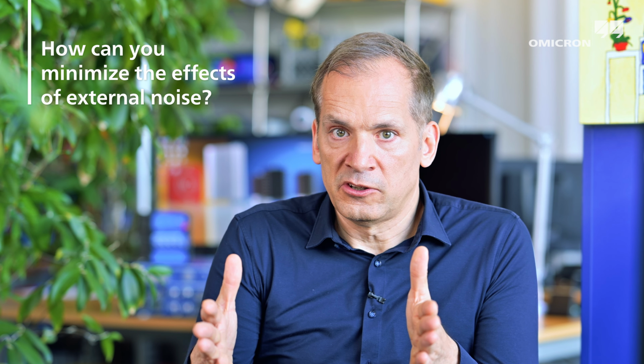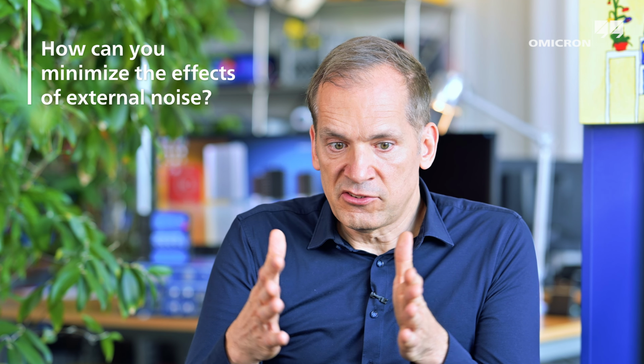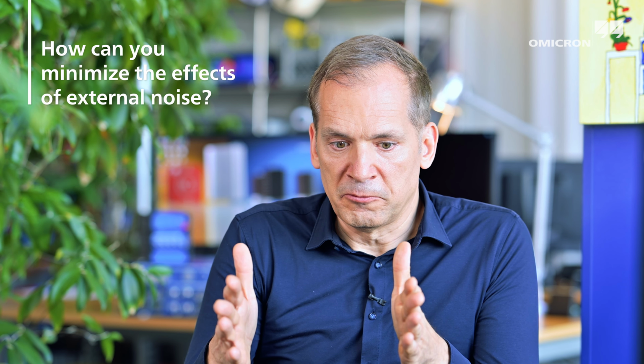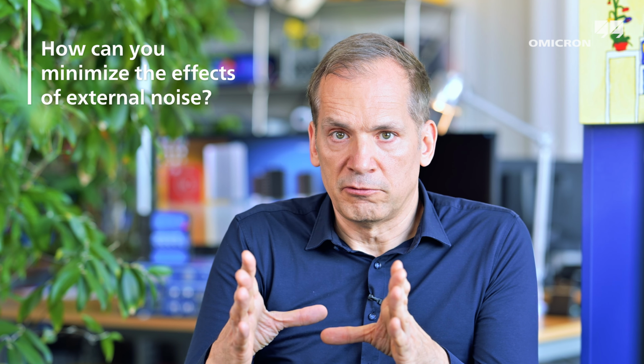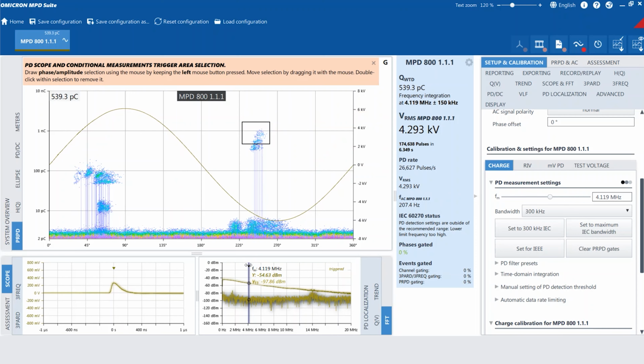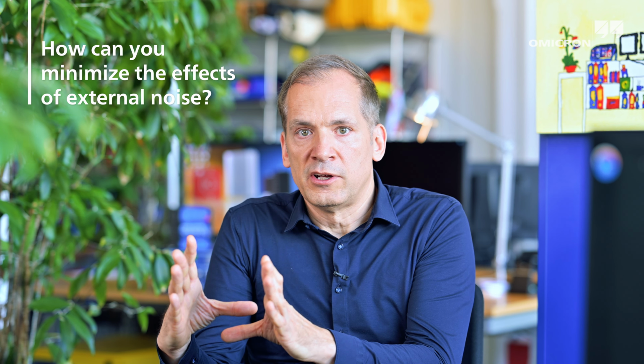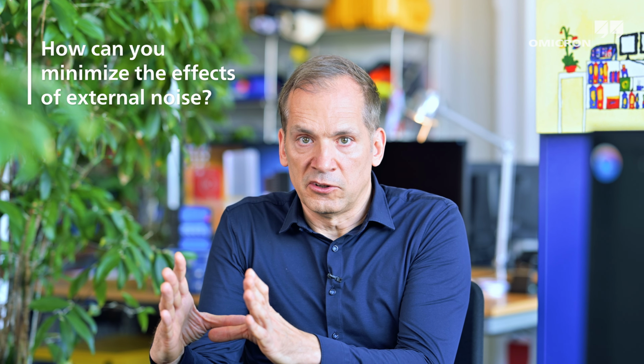Most real-world noise is spectrally limited. That is, it exists on the frequency spectrum within a confined frequency range. What we can do then is we can freely select a measuring frequency after analyzing that noise level and placing our measurement within a frequency range that is least affected by noise.